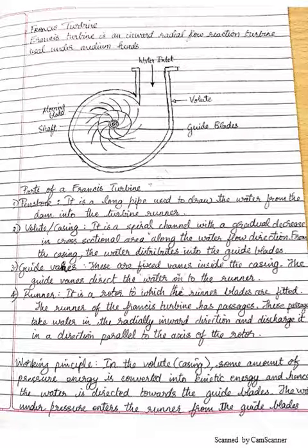Okay, so let's move now to the Francis turbine. The Francis turbine is an inward radial flow reaction turbine under medium heads. That is, the water stored above is medium head water, and it flows inward into the turbine in the radial direction. Previously, in the Pelton turbine, it was in the tangential direction, and now in the Francis turbine it moves radially and inwards. That's the fundamental difference. As you can see here, it's in the radial direction and water flows inwards.